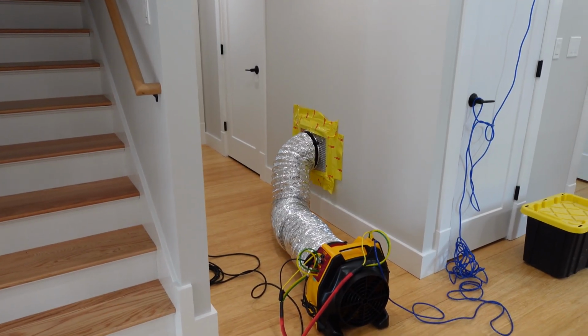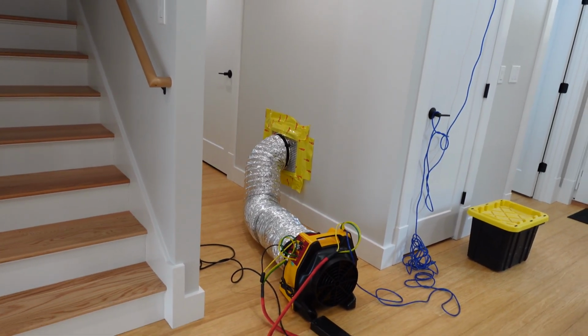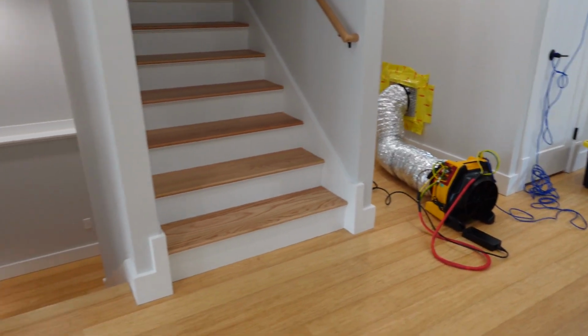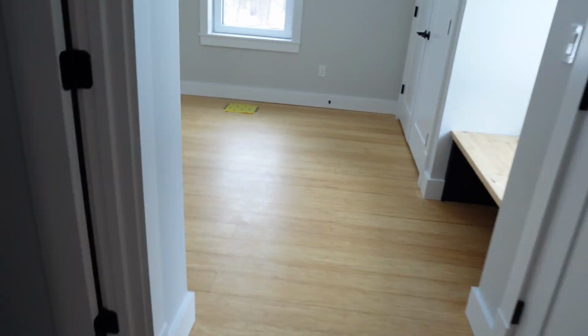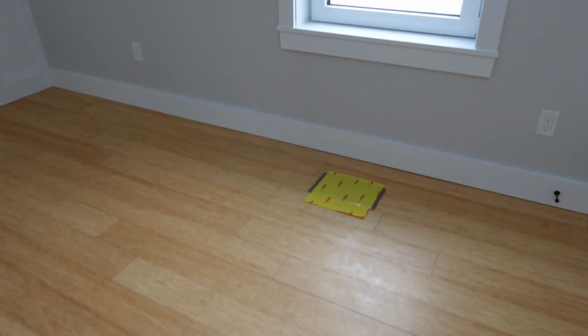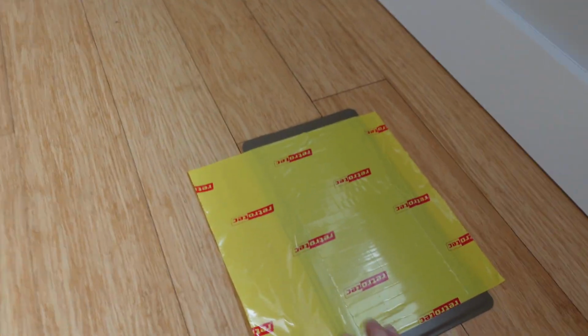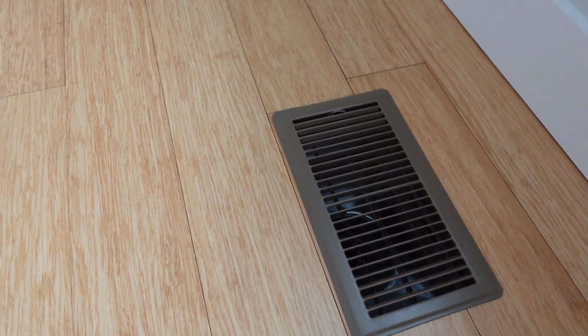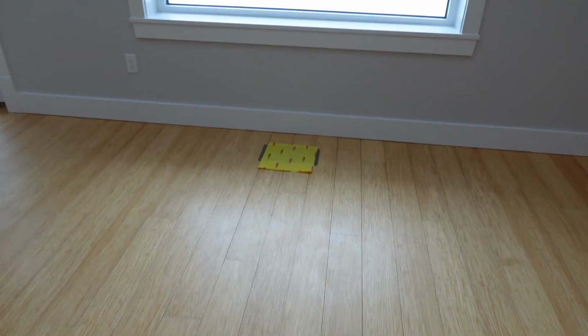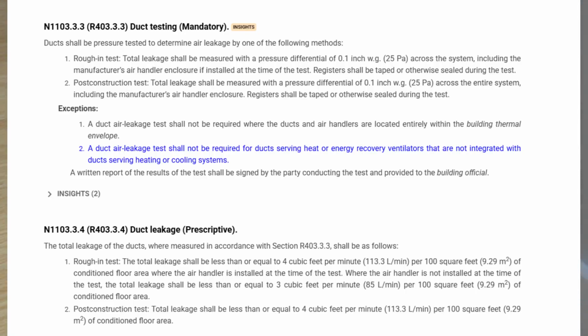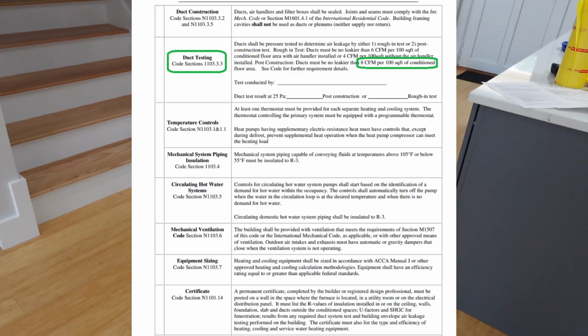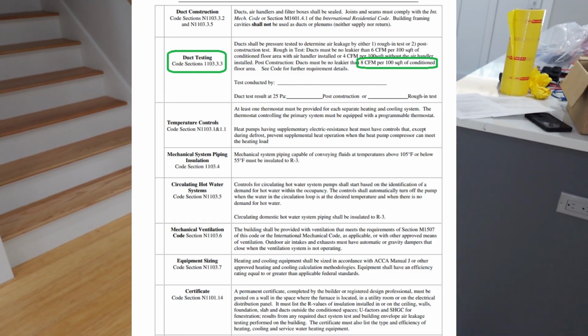Another reason why you want to have duct leakage testing is to ensure that it's working properly so that they're not leaking all of that conditioned air into an unconditioned space. So if you're going to pay to heat the air, it might as well go to where it's supposed to. The final reason you want to do this is because it's required by code. It's even required in New Hampshire, where it's currently 8 CFM per 100 square feet.